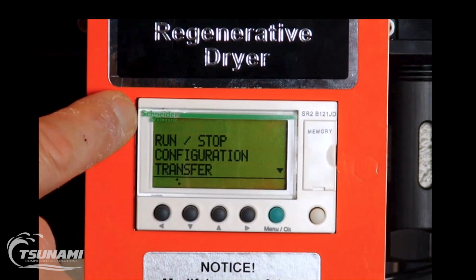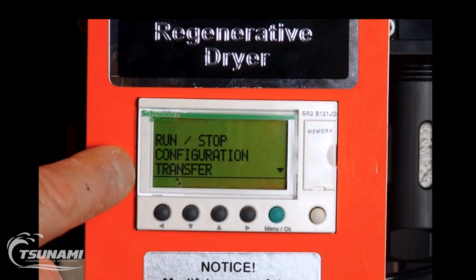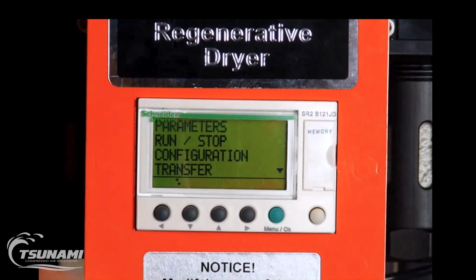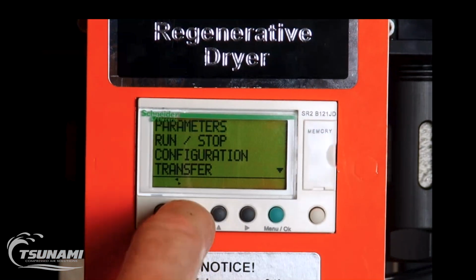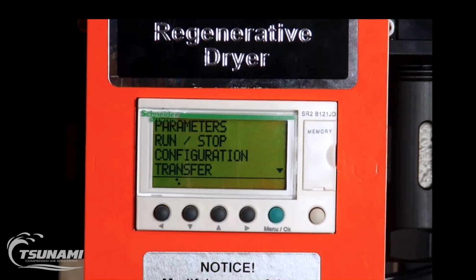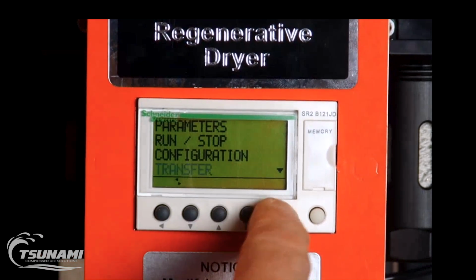So once we stop that program, we insert the memory, we go into parameters, run configuration. Now you see what's called transfer. Normally that wouldn't be there. So we would scroll down to transfer. It gives us that option. We hit OK.